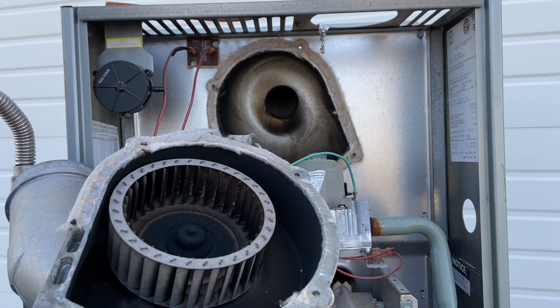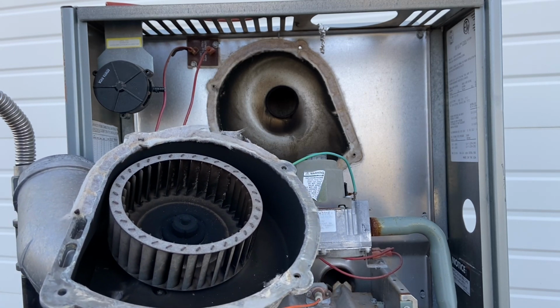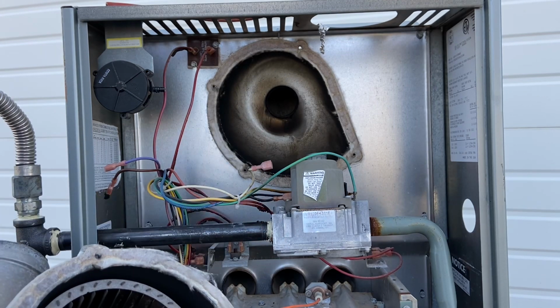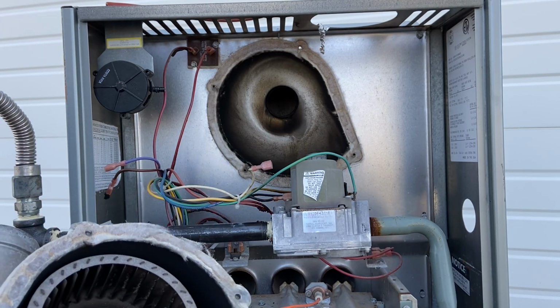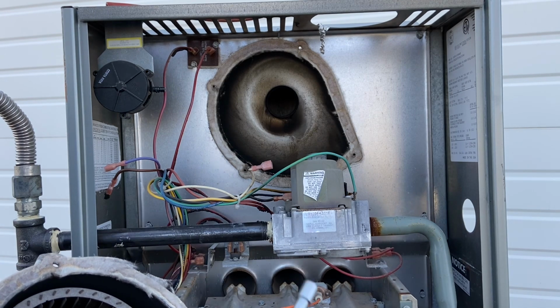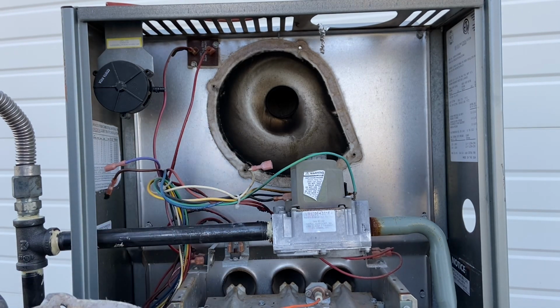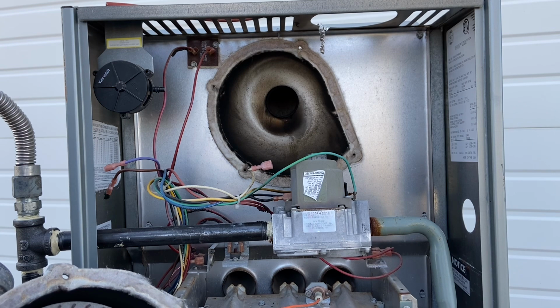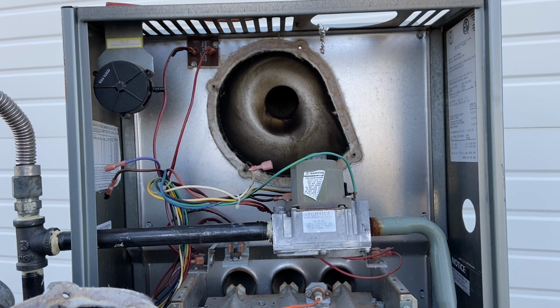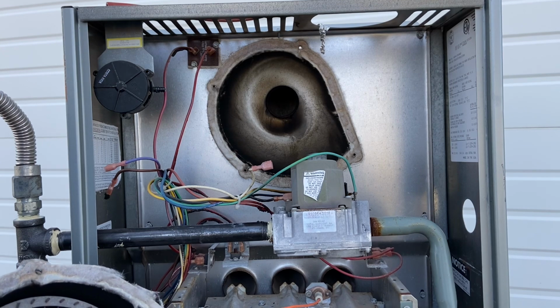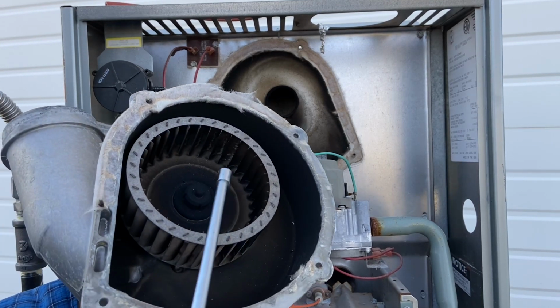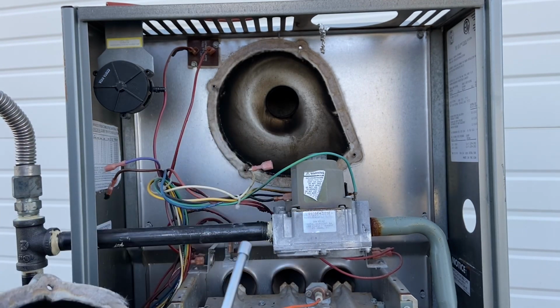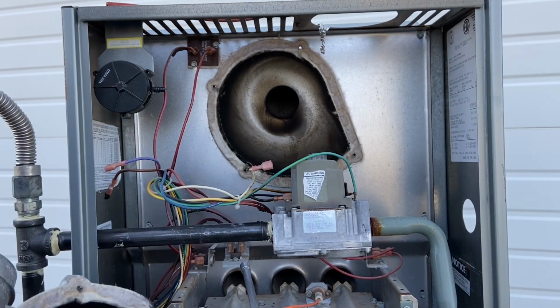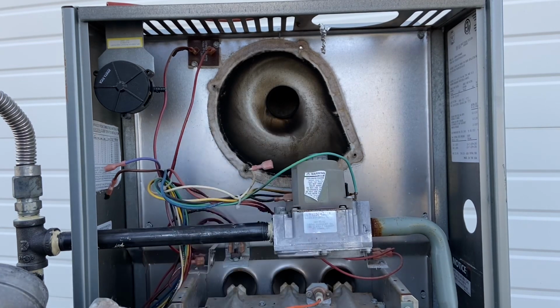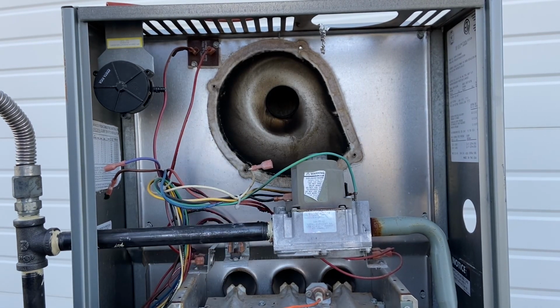So when a furnace runs without the proper gas air fuel mixture, without the proper conversion kits, these furnaces die a very early death, and that is not covered by any of the manufacturer's warranties. They say specifically in the manual that you have to follow the certain guide and their steps for converting these over. And also, many states require a separate certification for propane conversion. Texas requires you to go through the Texas Railroad Commission, and each state has their own requirements and regulations. And that's because of the significant damage here. This thing could run, the whole heat exchanger could soot up, and I've seen the flames come out of the heat exchanger, burn up the whole entire furnace just because they didn't have the conversion kit. Be safe, do it right.